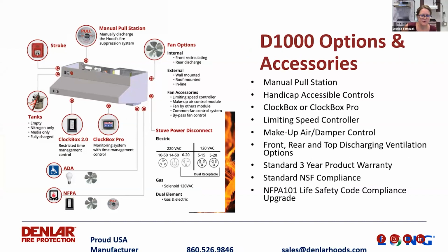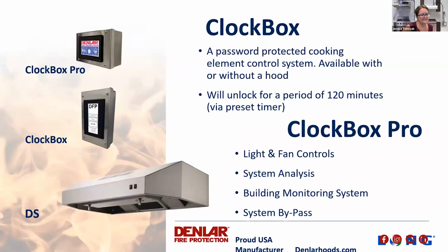So the D1000 is available with multiple options and accessories. As you can see here, we have the manual pull station, handicap accessible controls, and our ClockBox or the ClockBox Pro. We offer a limiting speed controller when it's not an NFPA 101 compliant model. That's a secondary speed controller that sets the maximum CFM output of the hood. We can work with a makeup air control system, or we can provide damper control if there is one. The ClockBox I will talk about next. I see that question. We also have multiple color options with both of our hoods.